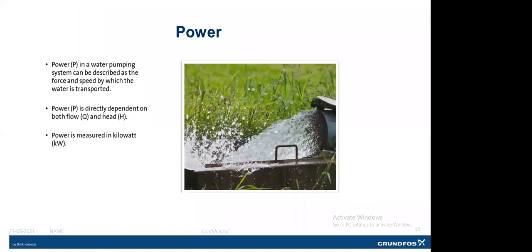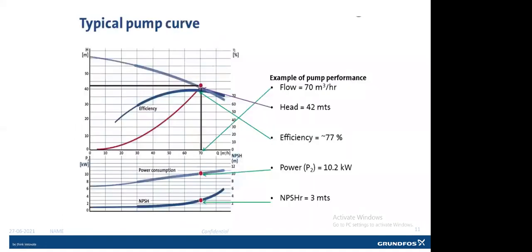Another term related to pump performance is power. Power is the main input for driving the pump, and it is measured in kilowatts, and it depends on the flow and head. As flow and head increase, power consumption increases. So we'll discuss the pump curve. We come across the pump curve, and we'll discuss it in detail.